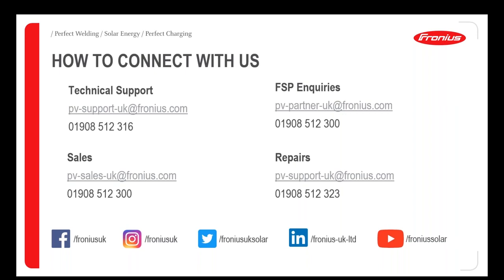Brilliant. And then we've got, if export limitation is not available for the TS range, what was the setting of export level for the 3,680 watts if not export limitation? So yeah, to clarify, export limitation is possible with the TS100. So that's fully compliant with G100 for export limitation. So the figure of 3,680 watts, that was the setting for export on the system as an example. That could be 0 if you have a 0 export site. But yes, very important that both of the smart meters you've seen today, the TS100 and the UL240, are both compliant with G100 for export limitation.